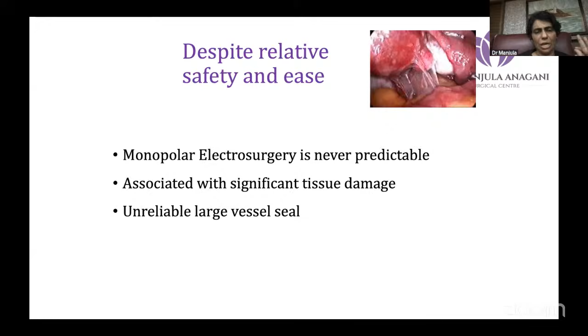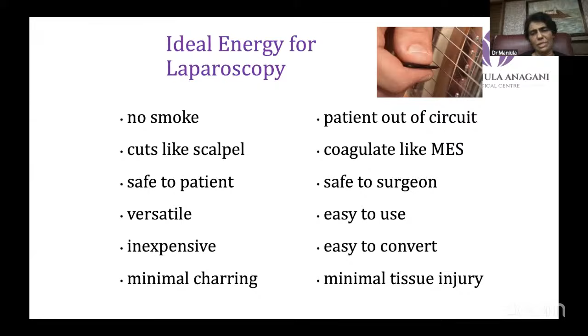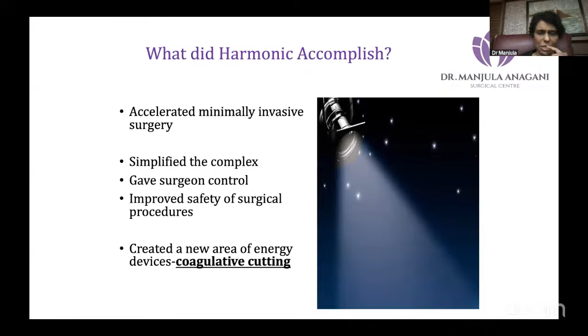So despite relative ease, monopolar is never predictable. It causes significant damage and an unreliable seal. But the ideal is something with no smoke. What we want is minimal charring, easy to use, easy to convert. The best thing is only the harmonic, which has accomplished this because it causes coagulative cutting.